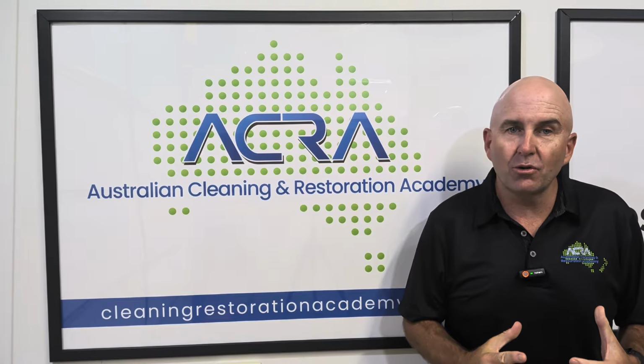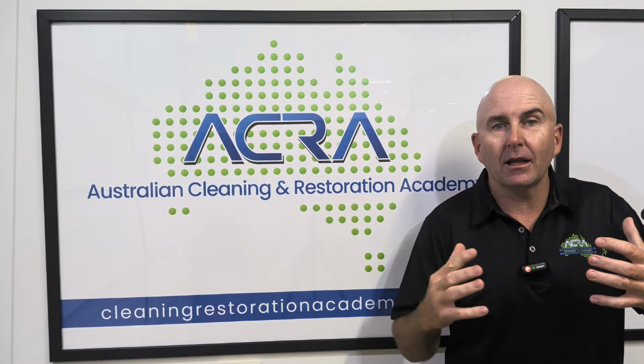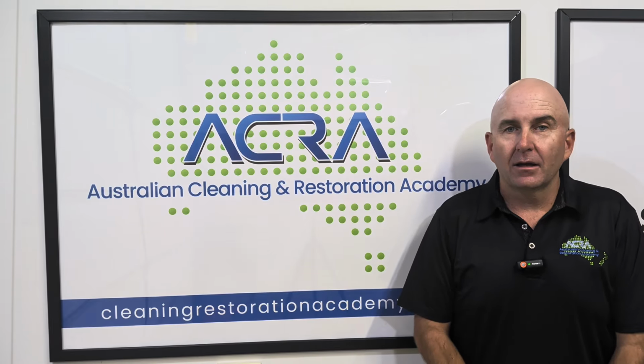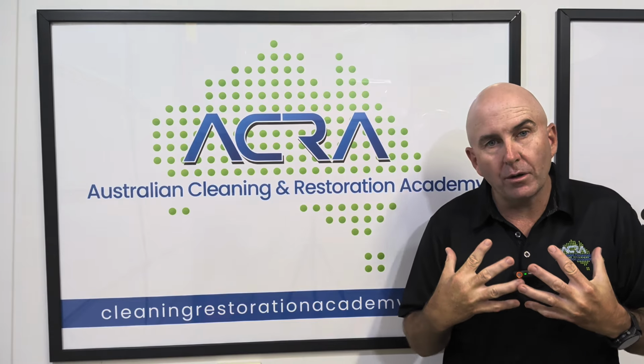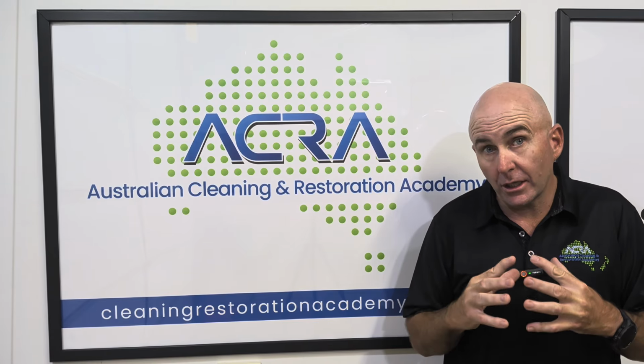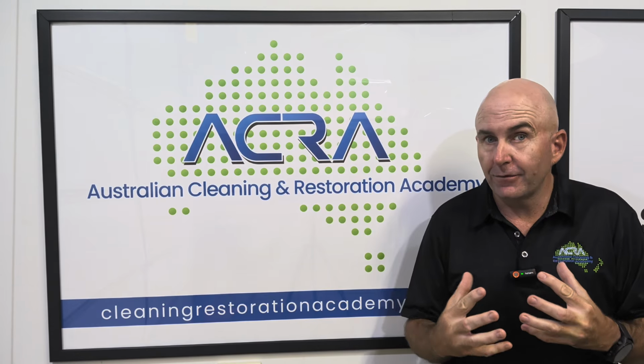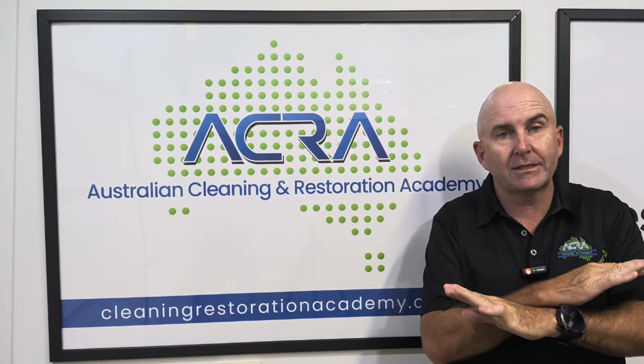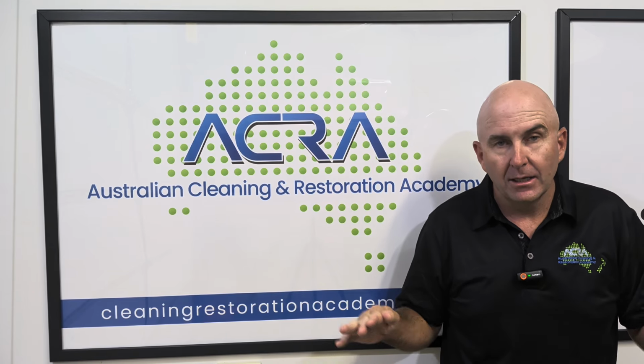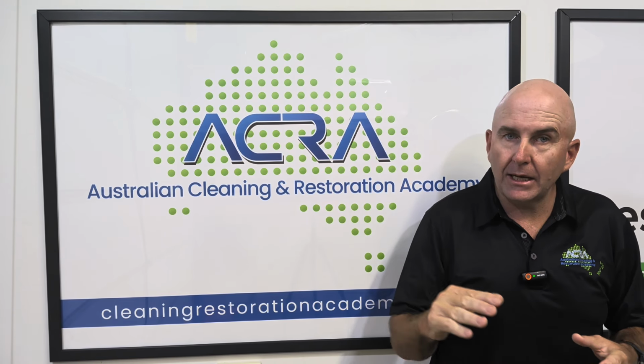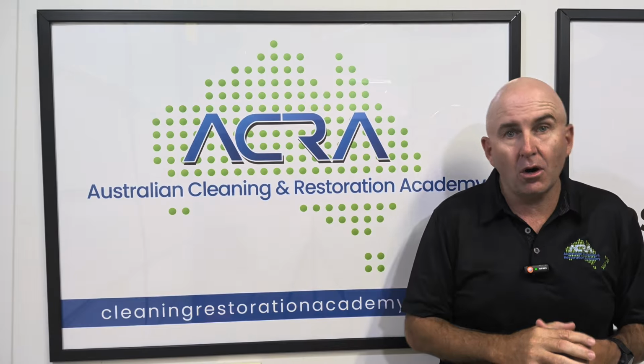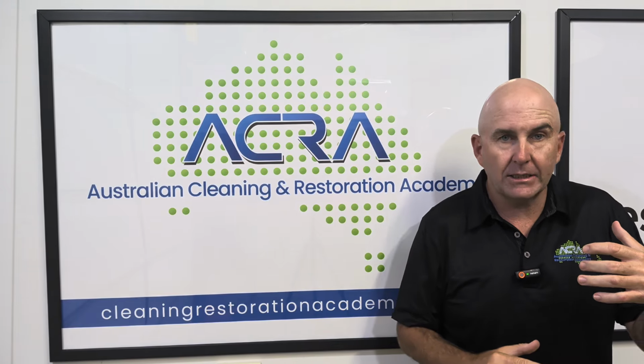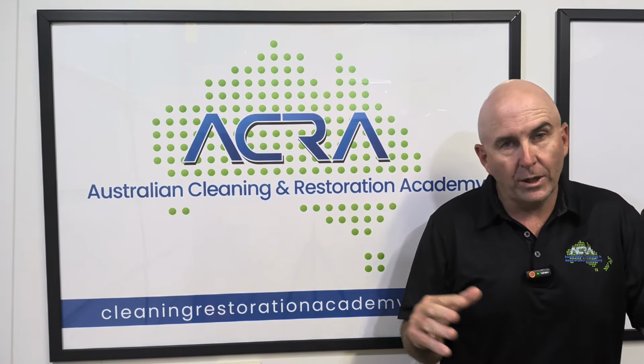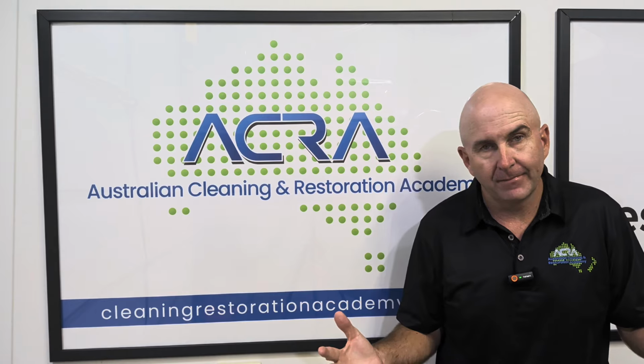Well, I'm here today to talk to you about moisture meter language. I see a lot of reports from a lot of trained technicians from insurance companies that do not make sense whatsoever. For example, some people are saying the Gyprock is 15% dry. Some people are saying it's 3% wet. Which one of those is correct?